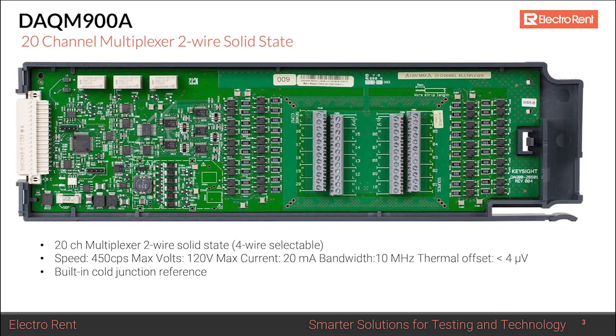The DAQM900A is a 20-channel solid-state multiplexer, likely using FETs, offering 450 channels per second and a bandwidth of 10 MHz at up to 120 volts. It includes a cold junction reference for thermocouple use. The thermal offset is larger than the 901A, but if you need to fit a few more thermocouples into a system and space is limited, the DAQM900A is a good option.